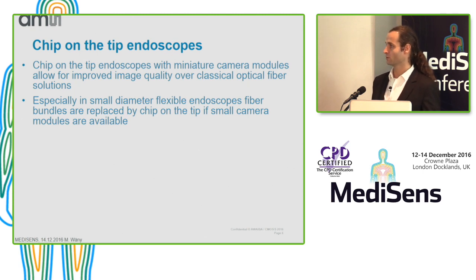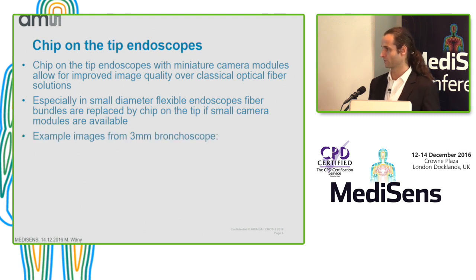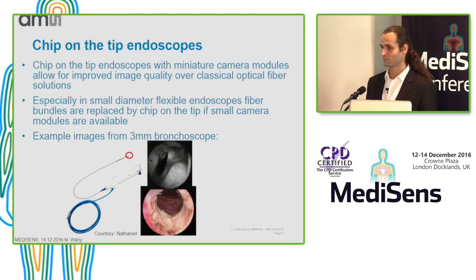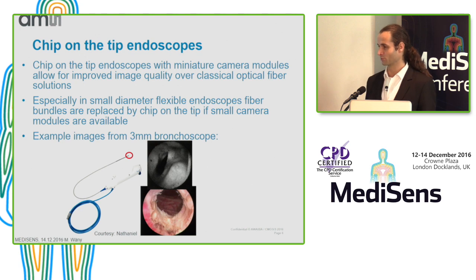Especially in small-diameter flexible endoscopes, nowadays we have a clear shift from fiber bundles to chip-on-the-tip endoscopes, mainly driven by enhanced image quality. You can see two images side by side from a fiber bundle endoscope and from a chip-on-the-tip endoscope. It does not take a lot of words to describe on which image you can see more, where you can make a better diagnosis and ultimately a safer surgery.